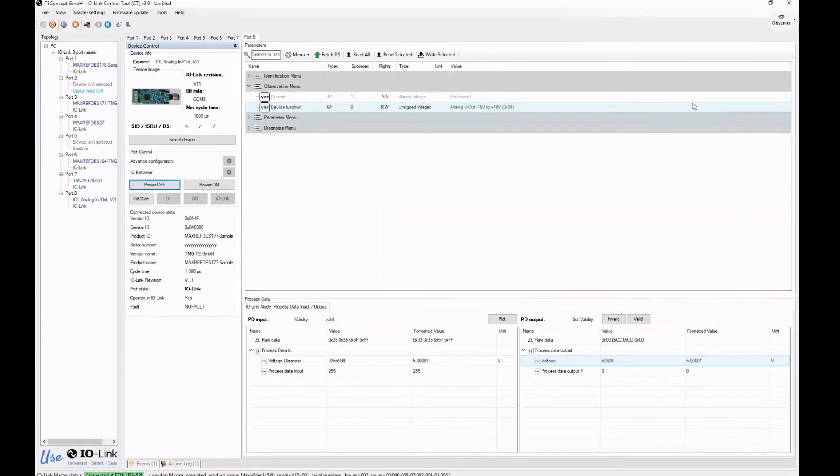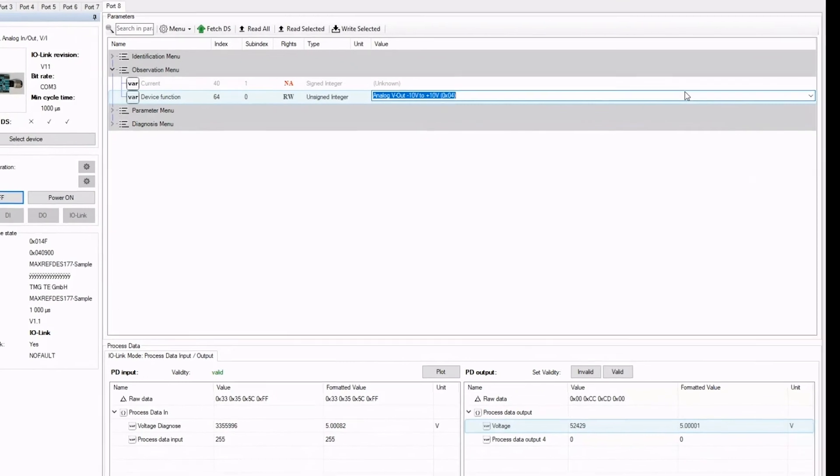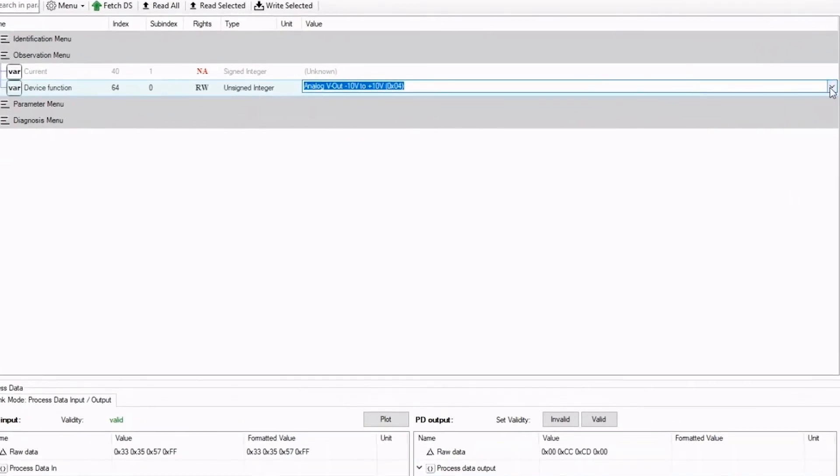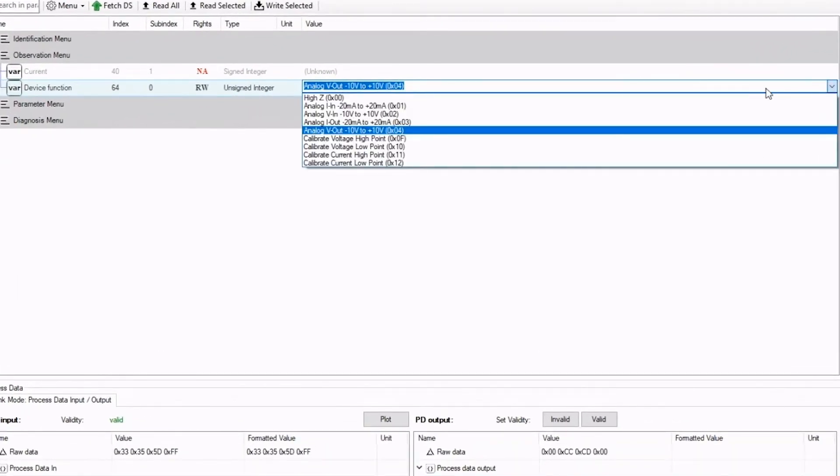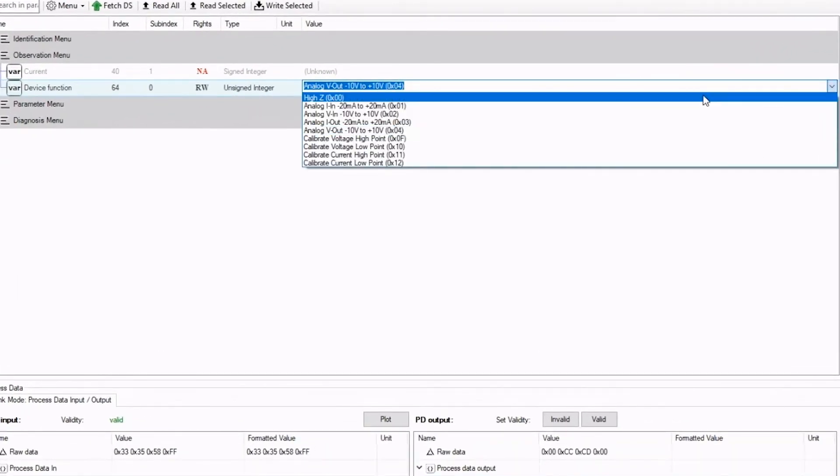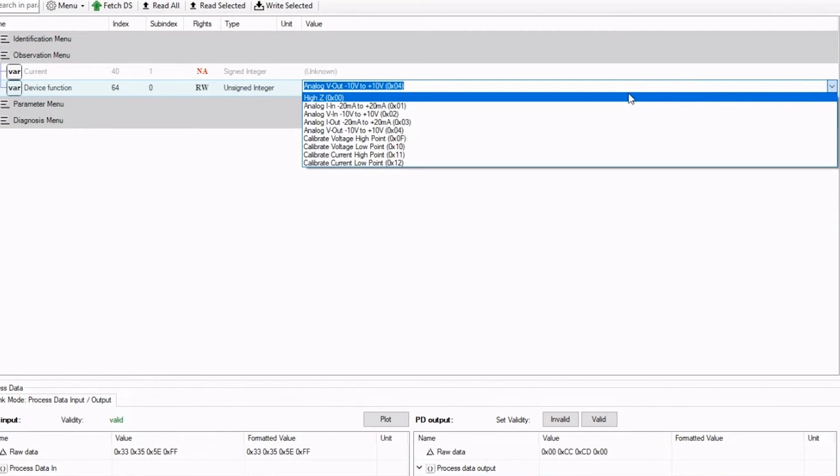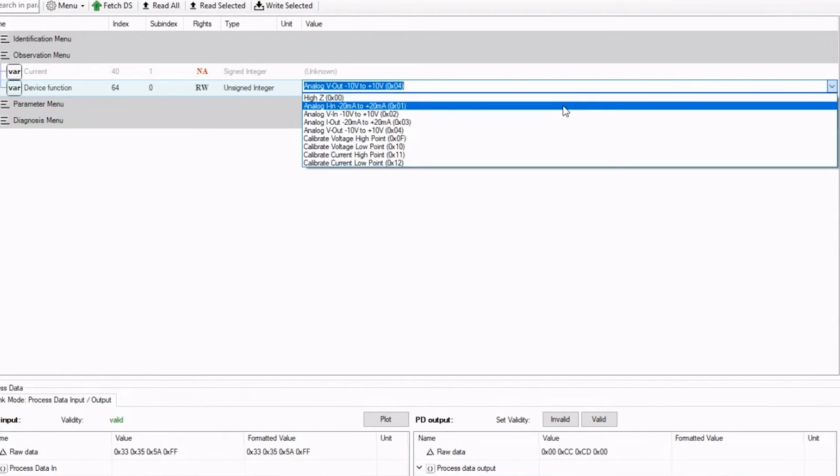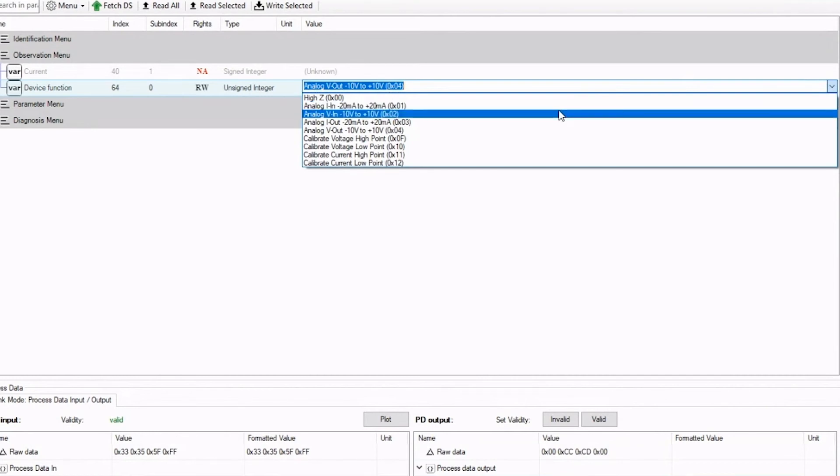And now I want to show the modes. So this board supports high Z mode, of course, which is very low leakage in off mode. And then we have a current input mode, which is minus 20 milliamp to plus 20 milliamp. Then we have a voltage input mode, which is minus 10 volt nominal to plus 10 volt.